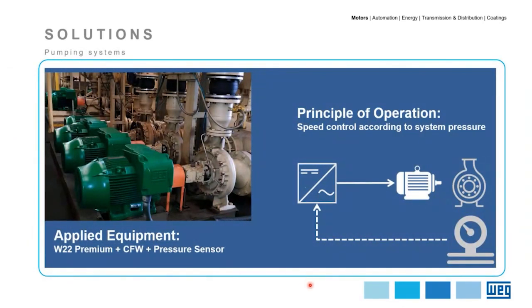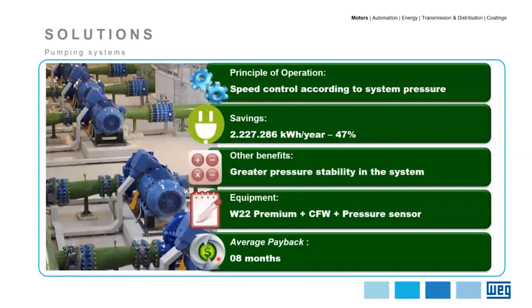This is a typical pumping system where the principle of operation is controlling the speed of a motor-pump according to system pressure. For this application, we used a WEG high efficiency motor, a WEG inverter, and a pressure sensor connected to the inverter to provide feedback to the PID controller. With this implementation, we achieved about 47% energy saving and great pressure stability in the system. The average payback for this application was about 8 months.